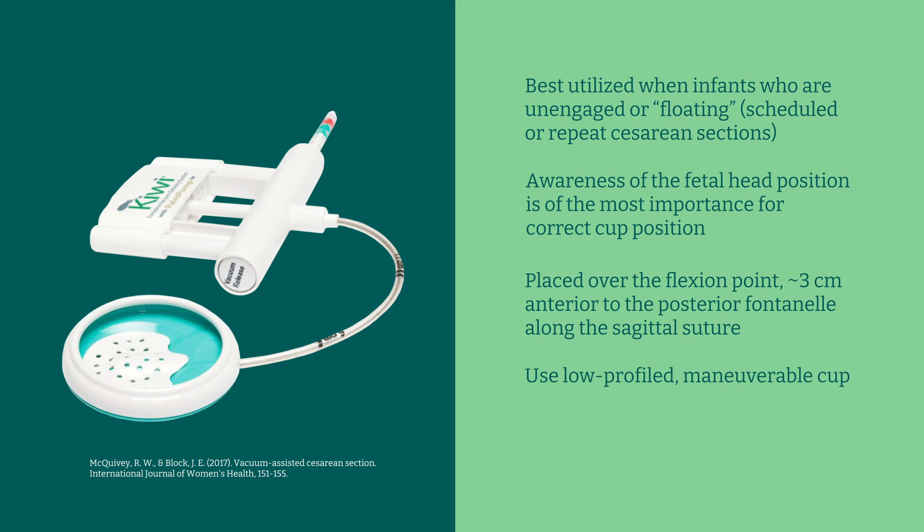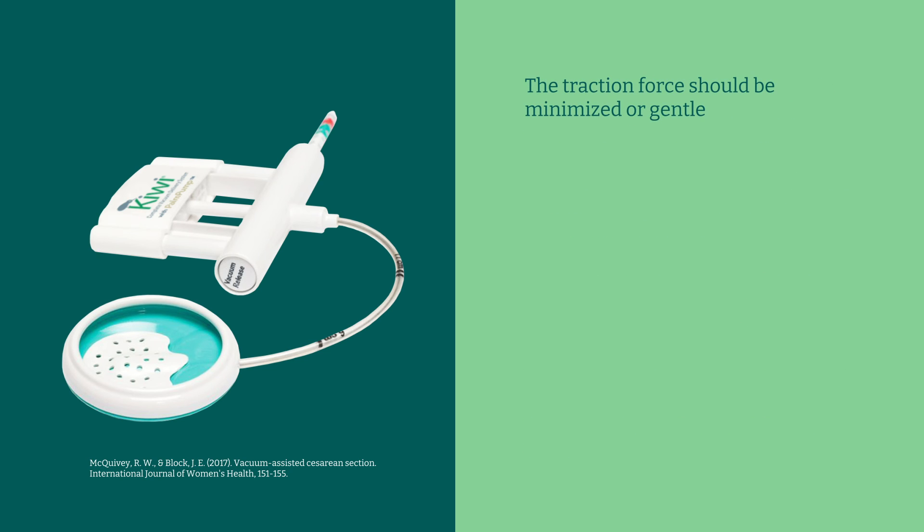Use low-profiled maneuverable cup. Lower the table to lowest point or use a lift. The traction force should be minimized or gentle. Abandonment of a vacuum delivery should be considered.